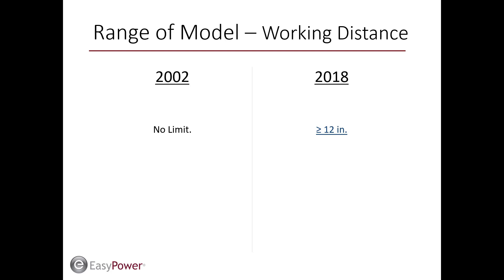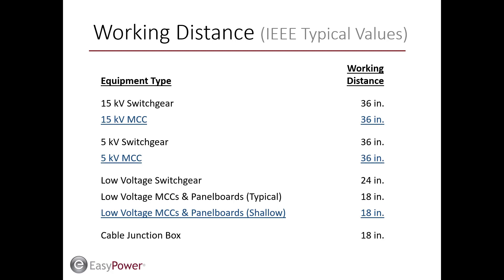The new standard now includes a minimum working distance of 12 inches as a limitation to the model range. Any smaller working distances could place a worker within the range of the actual arc plasma cloud, and the effect of direct contact with the plasma cloud is not considered in the arc flash model. Similar to the previous standard, IEEE provides typical working distances, with typical values equivalent to those from 2002 plus additional equipment types from the 2018 model.